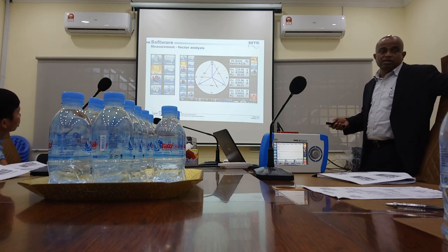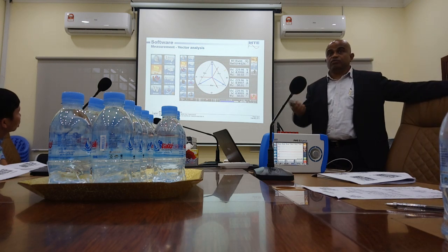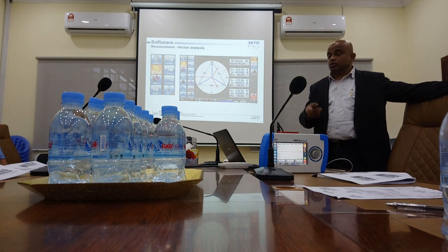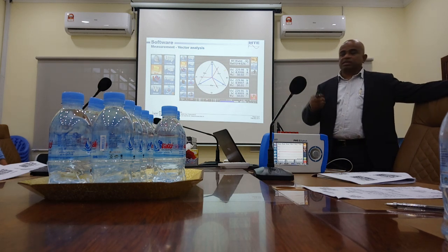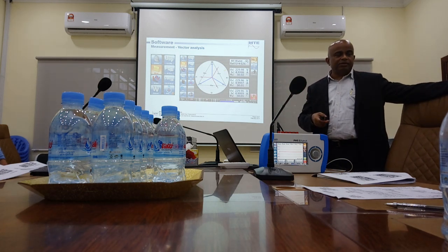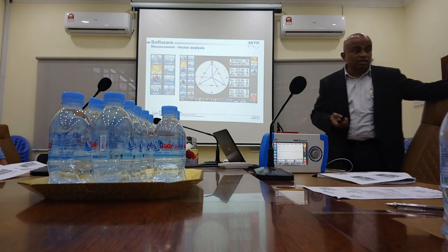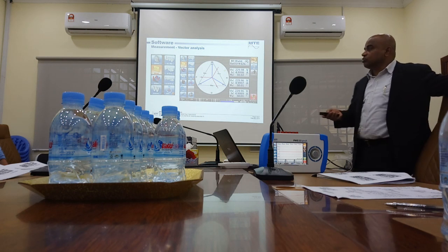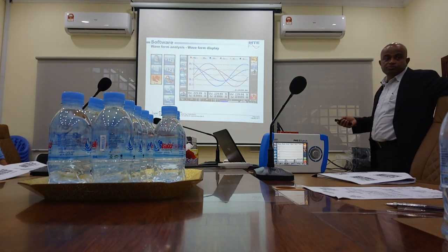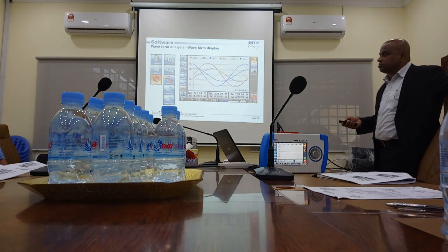Sometimes you see a very bad waveform. Like when I go to the site, I see the waveform. If the waveform is very bad, you know something is wrong there. Maybe the customer load is very bad, or maybe something is wrong with the CT, or anything like that. So you have to monitor the waveforms also. Okay, it's good to know.